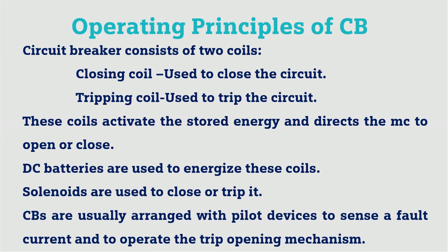There are two coils used in this ACB: a closing coil, which is used for closing the circuit, and a tripping coil, which is used for tripping. These coils activate the stored energy and deflect the moving contact for open or close. DC batteries are used to energize these coils.